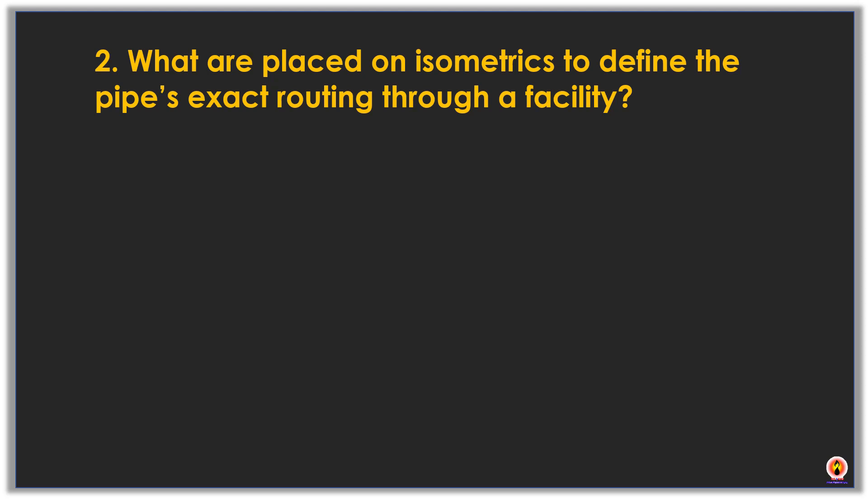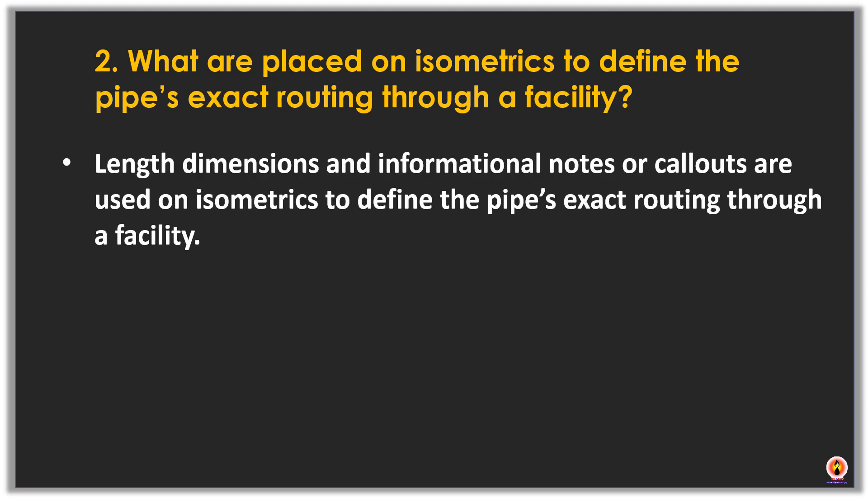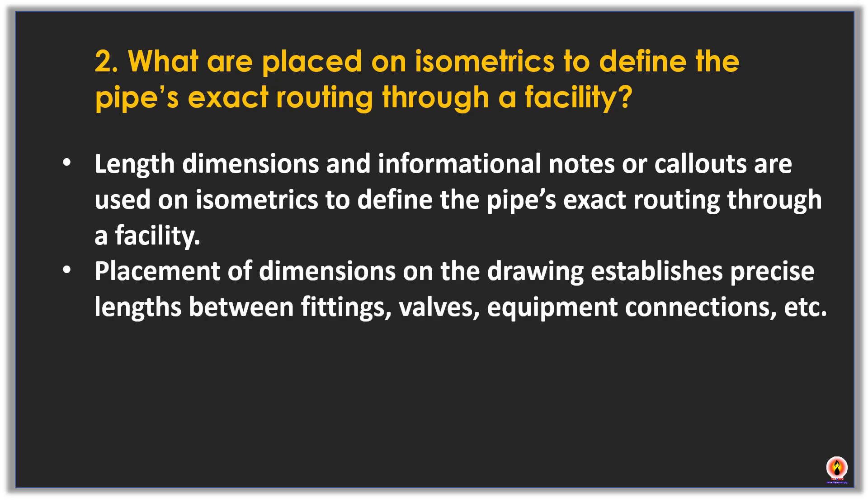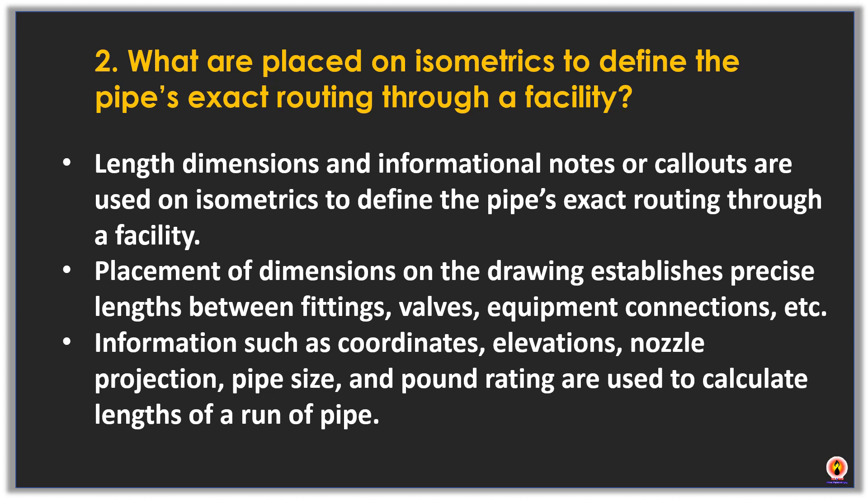Length dimensions and informational notes are used on isometrics to define the pipe's exact routing through the facility. Placement of dimensions on the drawing establishes the length between fittings, valves, equipment connections, etc. Information such as coordinates, elevations, projections, pipe size, and pound rating are used to calculate the length of runs of pipe.